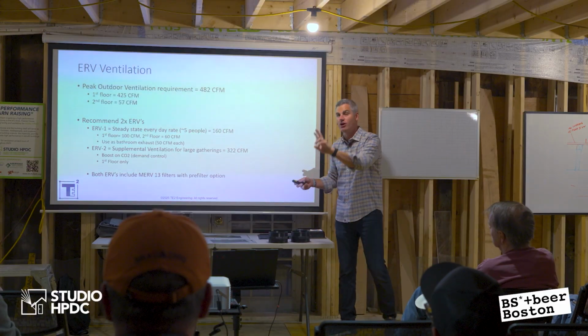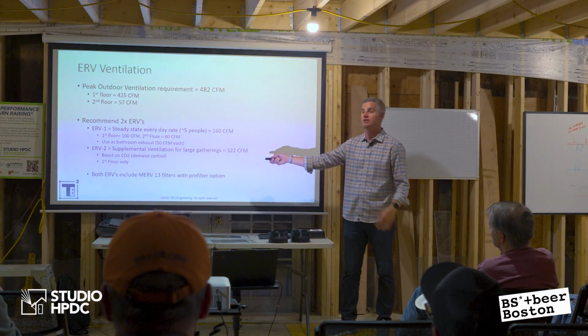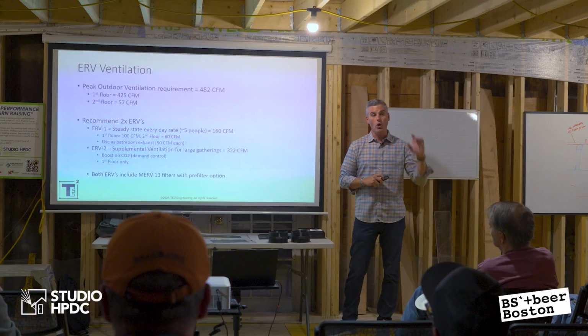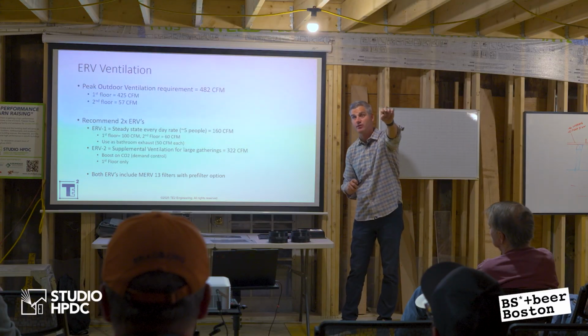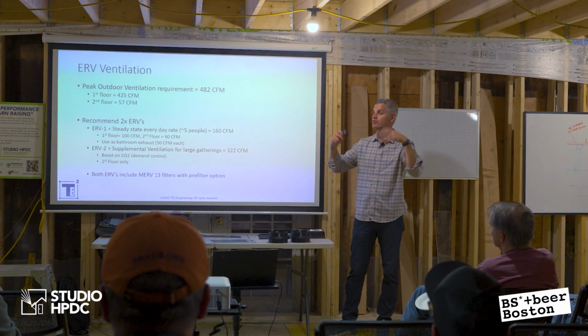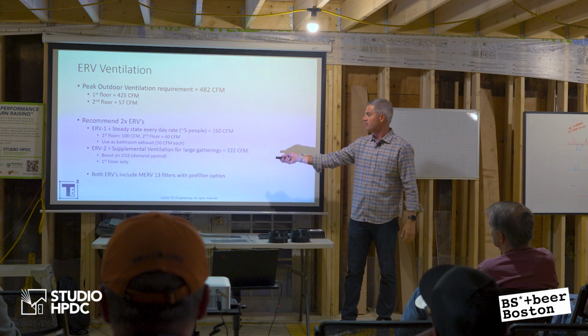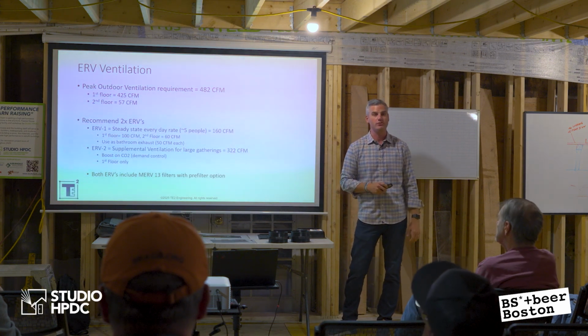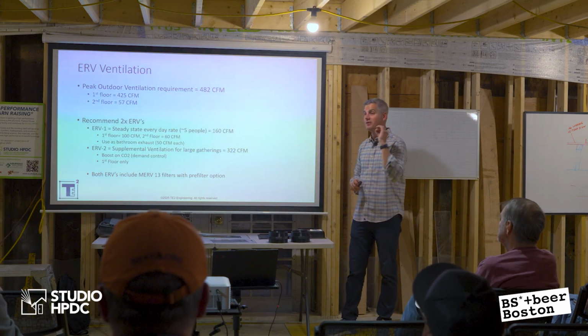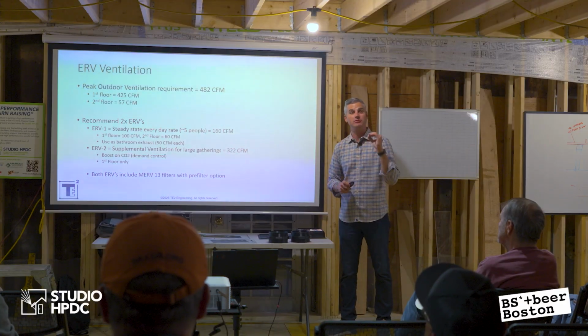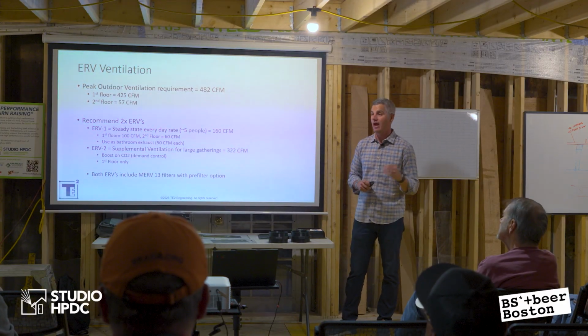But then I add a second ERV, and the second ERV is for supplemental ventilation based on large gatherings. The only time it's going to kick on is when a CO2 sensor in the back senses that the CO2 is rising in the space. And when it does, it's going to have the ability to boost up, in this case, to 322 CFM. It's only going to be designed to run when it needs to, based on demand control, based on when there's a large gathering in the space.